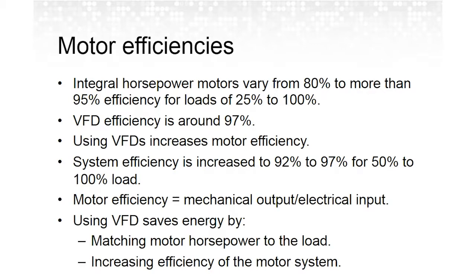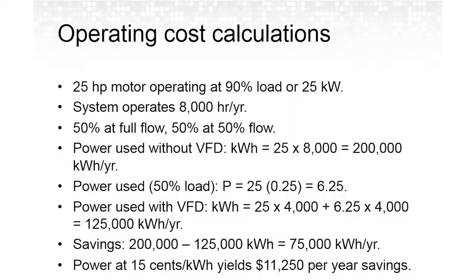Motor efficiency is defined as mechanical output divided by electrical input. So that's how you can calculate your system efficiency. So using a VFD saves energy by matching the motor horsepower to the load and increasing the efficiency of the motor system.